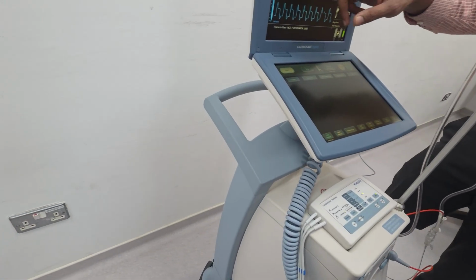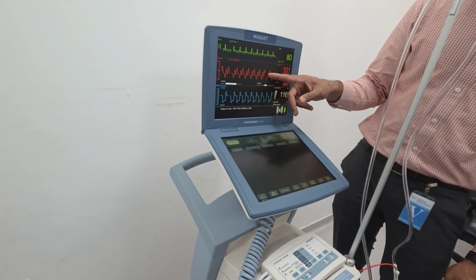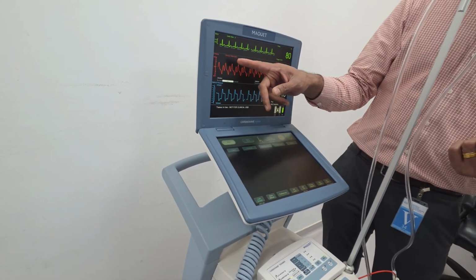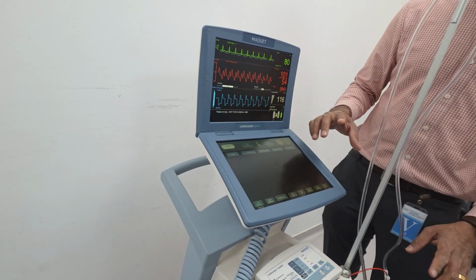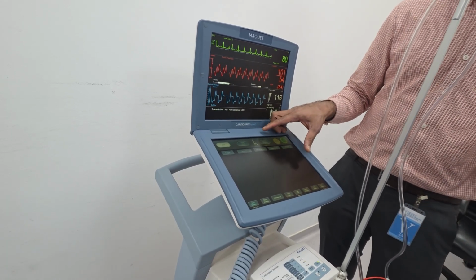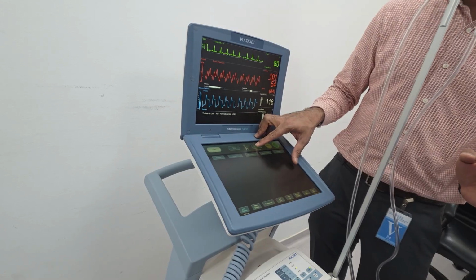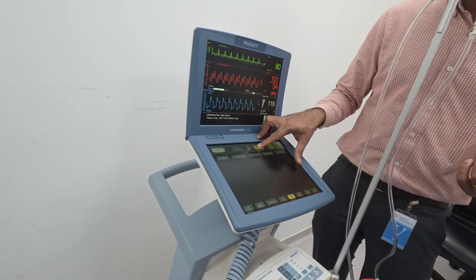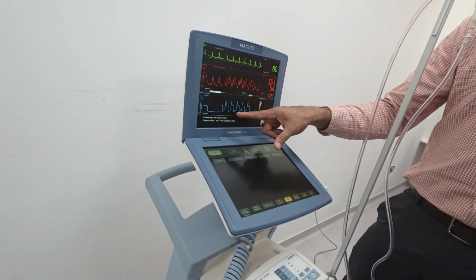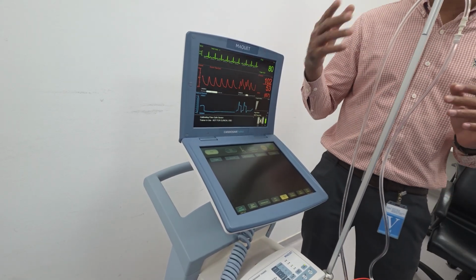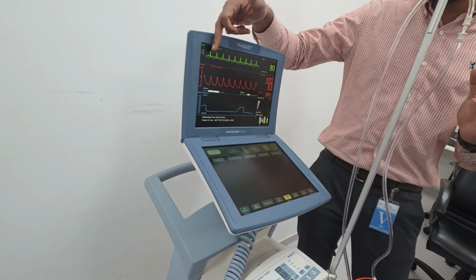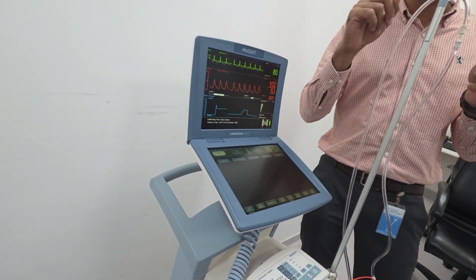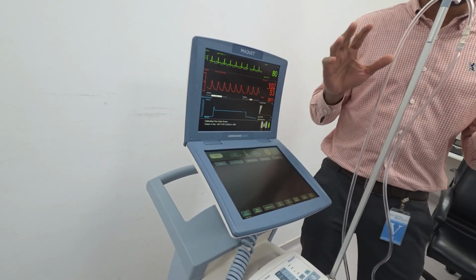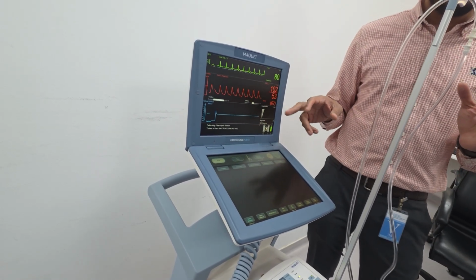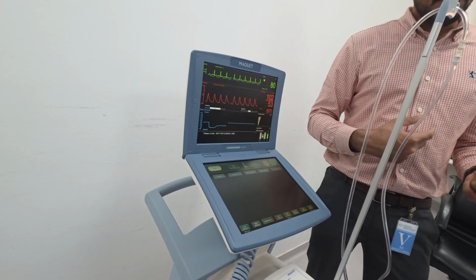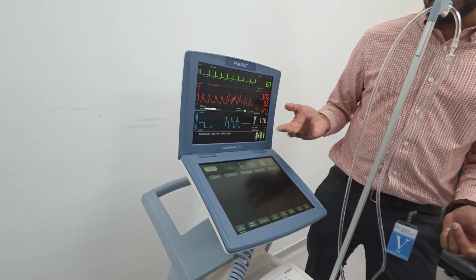As I told you, the machine will keep on checking the pressure waveform for the dicrotic notch position. If your arterial waveform is not good, it will do automatic calibration every 2 hours, same like CS300. But if you wish to do a calibration for your fiber, you can hold it here, like zeroing. Just do it here. Sometimes it will give you unable to update the timing. That means the machine is triggering based on ECG, but the dicrotic notch position is not being detected because of noise in the arterial waveform. So just calibrate it. Like if you are using a normal balloon, you need to flush it, right? Same way, you just need to calibrate.